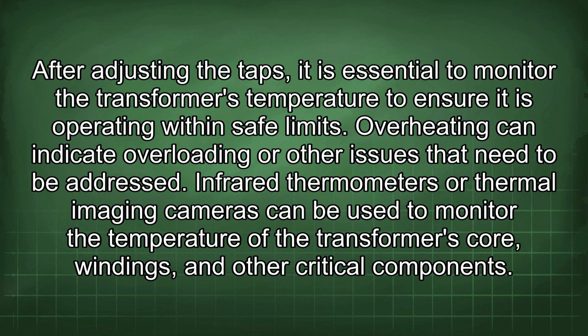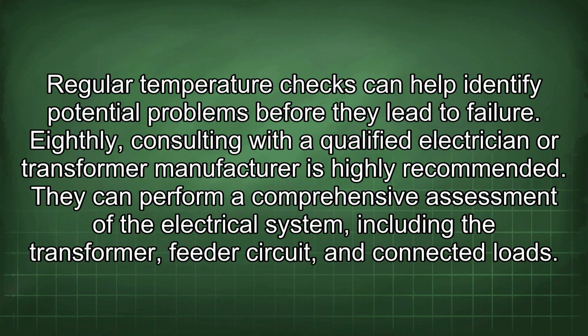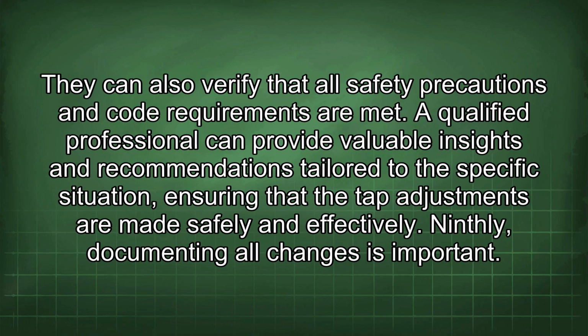Infrared thermometers or thermal imaging cameras can be used to monitor the temperature of the transformer's core, windings, and other critical components. Regular temperature checks can help identify potential problems before they lead to failure. Eighthly, consulting with a qualified electrician or transformer manufacturer is highly recommended. They can perform a comprehensive assessment of the electrical system, including the transformer, feeder circuit, and connected loads. They can also verify that all safety precautions and code requirements are met.